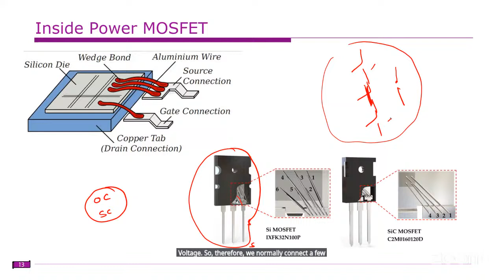So we design the failure mechanism such that it should be short circuit. Then we have only two devices left, and those two are supposed to withstand the voltage. Therefore we normally connect a few more switching devices as redundant, so if one device fails, the burden is not shared unevenly among the other devices. If not properly maintained, the other devices may also fail, so we connect extra devices for safer operation.